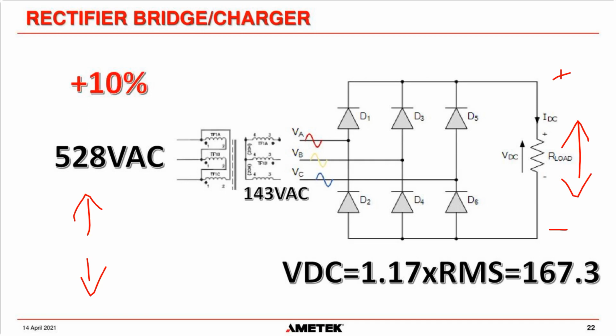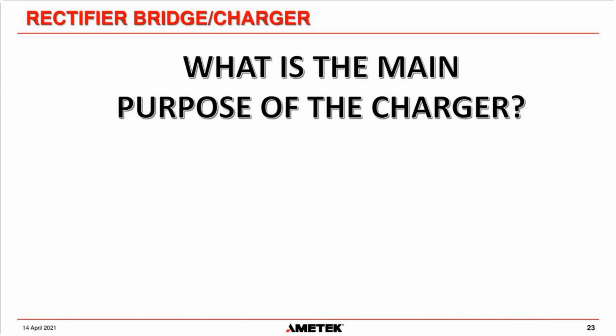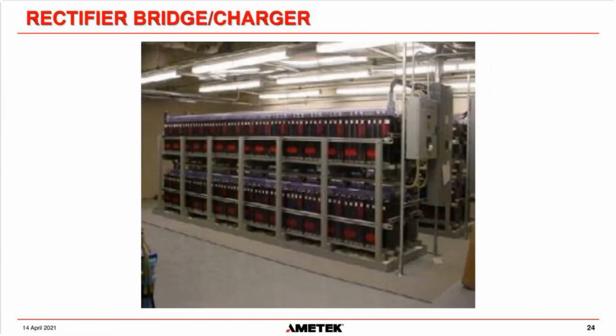So we cannot use diodes in our bridge because it gives us no control for those swings in the input voltage, letting the output voltage go up and down basically in sync with it. So we need something to prevent that. Because what is the main purpose of the charger? People often forget this. A lot of people think it's to keep your load circuits energized and make sure the switchgear doesn't shut down. No, actually, the main purpose of a charger is to charge your batteries.